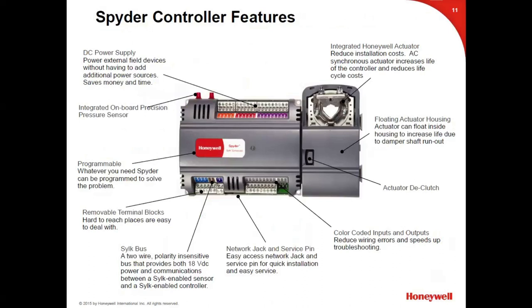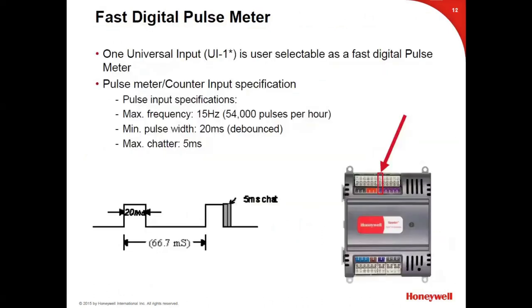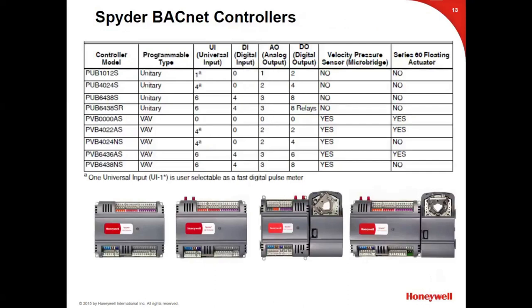Color-coded inputs and outputs reduce wiring mistakes, and the terminal blocks are removable. Each one of our controllers has a universal input that can be used as a pulse to accept pulse counts for meters. This is a chart from our documentation showing our BACnet line — the PUB and the PVB — with I/O counts and controller specifics. The naming convention: the second character is 'U' for unitary, 'V' for VAV; the third character is 'B' for BACnet or 'L' for LON.